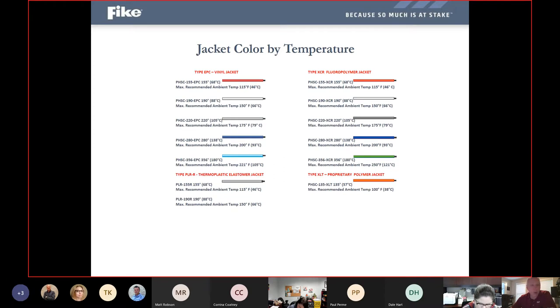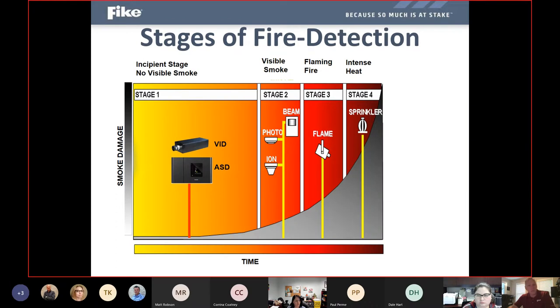And you can see that we do have a wide range of temperatures, as well as the outer jackets that allow it to be put into some extremely cold conditions or extremely harsh conditions, with maybe some toxic or caustic chemicals being in place there. So a lot of different types and temperatures of wires we can use to accommodate just about any environment that we want to detect in with linear heat detection. So that really touches on just a real quick overview of some of the advancements or different means of detection.